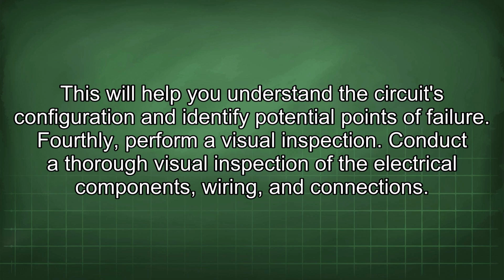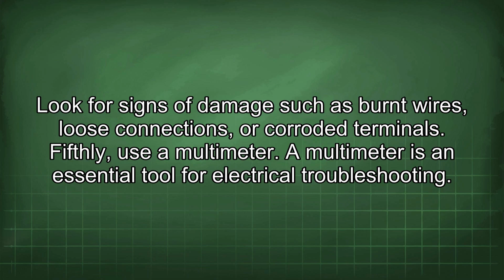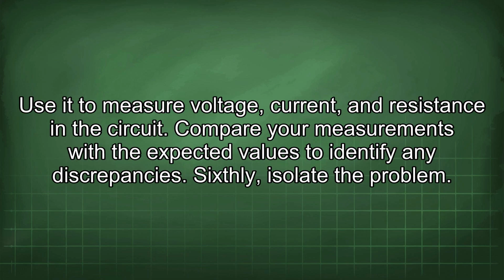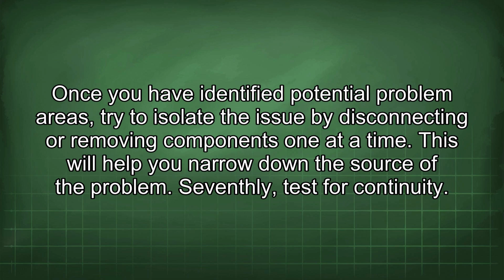Fourthly, perform a visual inspection. Conduct a thorough visual inspection of the electrical components, wiring, and connections. Look for signs of damage such as burnt wires, loose connections, or corroded terminals. Fifthly, use a multimeter. A multimeter is an essential tool for electrical troubleshooting. Use it to measure voltage, current, and resistance in the circuit. Compare your measurements with the expected values to identify any discrepancies. Sixthly, isolate the problem. Once you have identified potential problem areas, try to isolate the issue by disconnecting or removing components one at a time. This will help you narrow down the source of the problem.